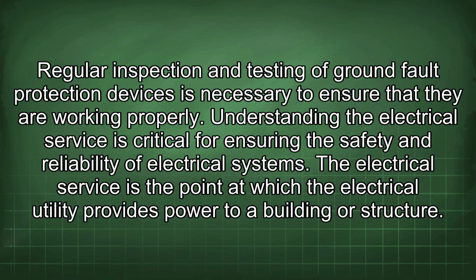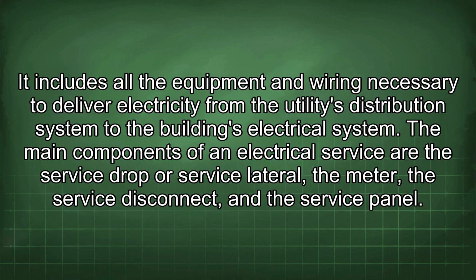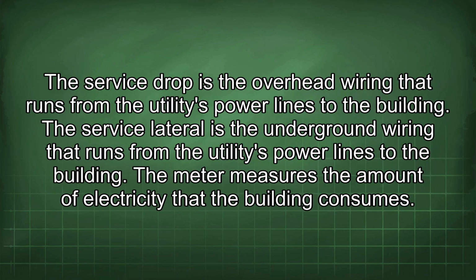The electrical service is the point at which the electrical utility provides power to a building or structure. It includes all the equipment and wiring necessary to deliver electricity from the utility's distribution system to the building's electrical system. The main components of an electrical service are the service drop or service lateral, the meter, the service disconnect, and the service panel. The service drop is the overhead wiring that runs from the utility's power lines to the building. The service lateral is the underground wiring that runs from the utility's power lines to the building.